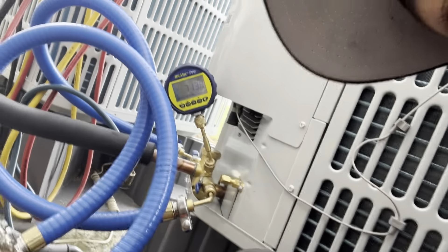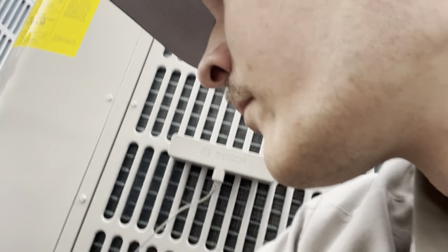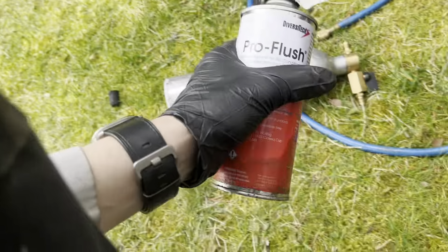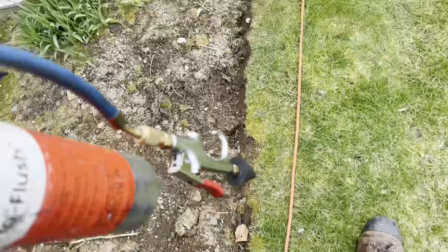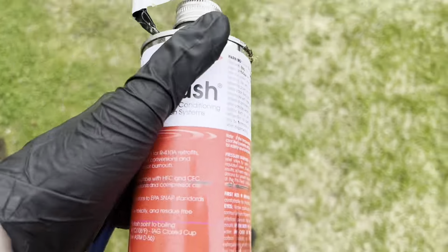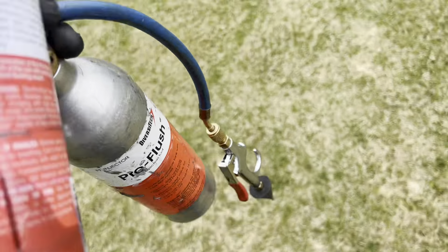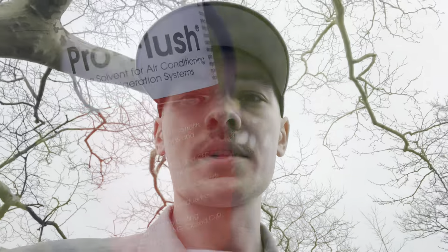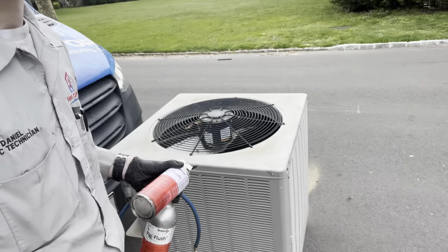It's 3:15 right now, vacuum at 713 microns. I'm gonna close the gas ballast and you can see it starts to drop more rapidly. Should be able to pull a good vacuum. We used the ProFlush solvent to remove the oil from the system, as well as the line set wiper, so we definitely got all the oil out, because this was an old R22 system.